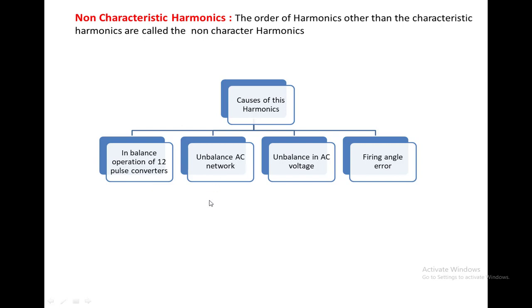Another cause is an unbalanced AC network. Each converter feeds power through a transformer, and a difference in the leakage reactance of the transformers generates non-characteristic harmonics. Also, because of unbalanced AC voltage, non-characteristic harmonics will be generated. The last cause is firing angle error — if there is a firing angle error between the two converters or within a single converter, non-characteristic harmonics will be generated.